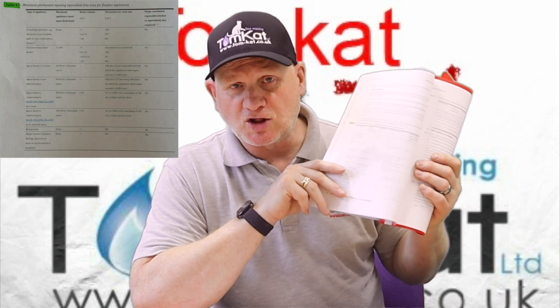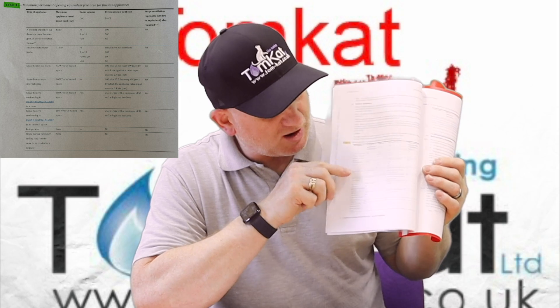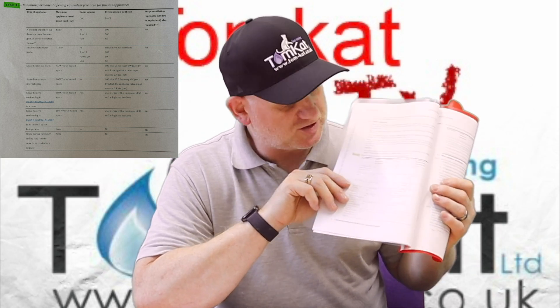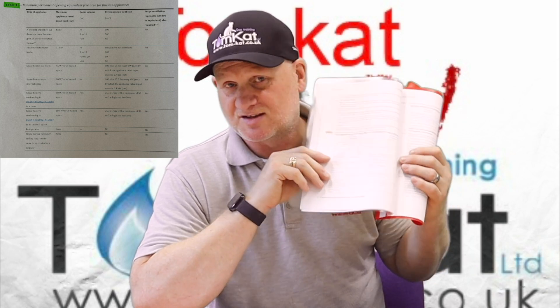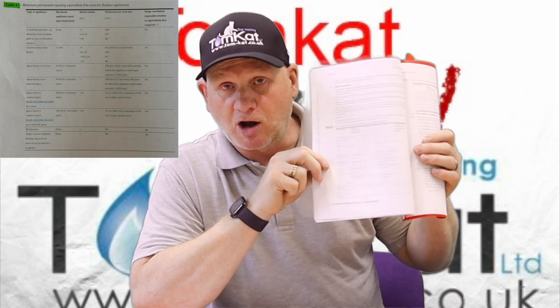Decommissioned SE ducts or U ducts are also considered a protected area, with attention drawn to building requirements for each relevant geographical location, including England, Guernsey, Isle of Man, Jersey, Northern Ireland and Scotland. Tables and figures have also been updated. Table 4 has been moved to page 12, where you'll now find all the information for flueless appliance ventilation, such as cookers, flueless water heaters and flueless space heaters.